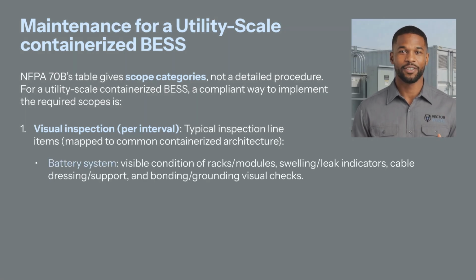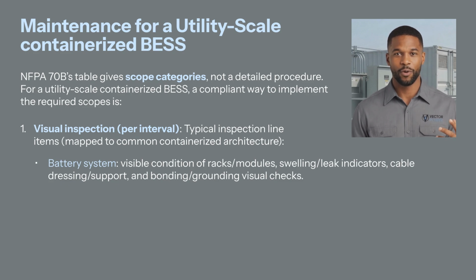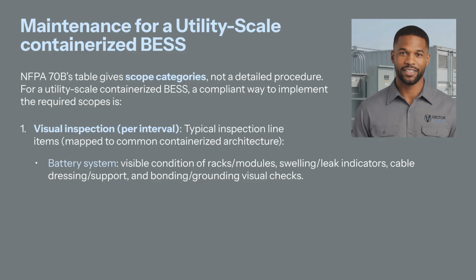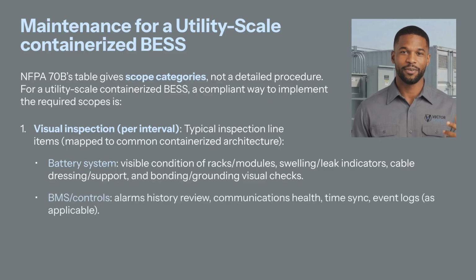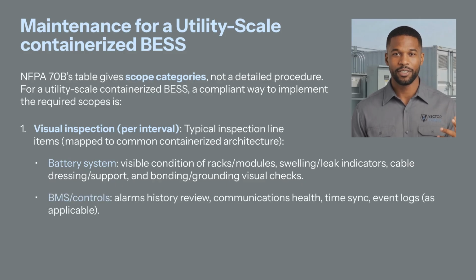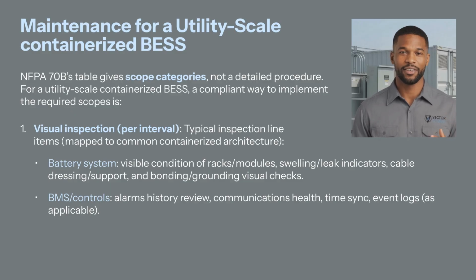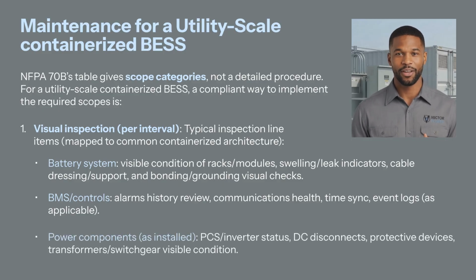Battery system. Visible condition of racks, modules, swelling, leak indicators, cable dressing, support, and bonding and grounding visual checks. Battery management system and controls. Alarms history review, communications health, time sync, event logs as applicable, and finally, power components as installed, PCS inverter status, DC disconnects, protective devices, transformers, switchgear visible condition.